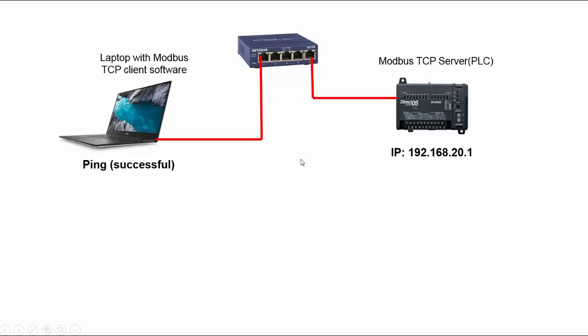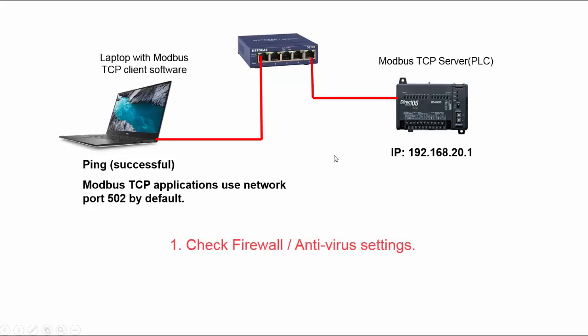What we have to remember is that Modbus TCP applications use network port 502 by default, and very frequently port 502 is blocked by default in a lot of network situations. So what I tell them to do is first of all check the firewall and antivirus settings on their computer, and nine times out of ten that is what is causing the issue.